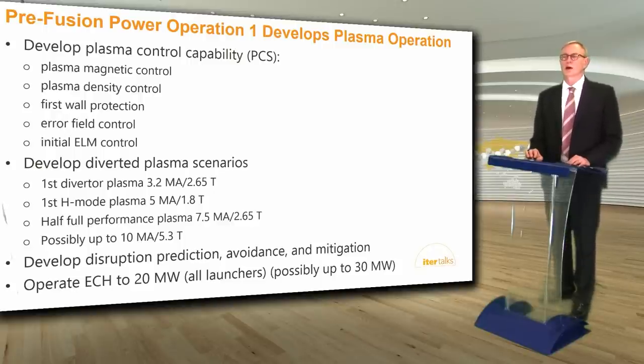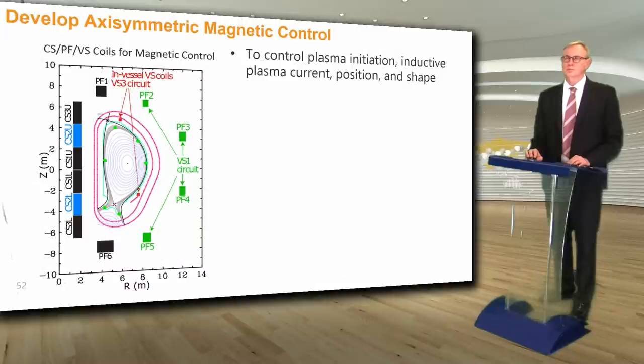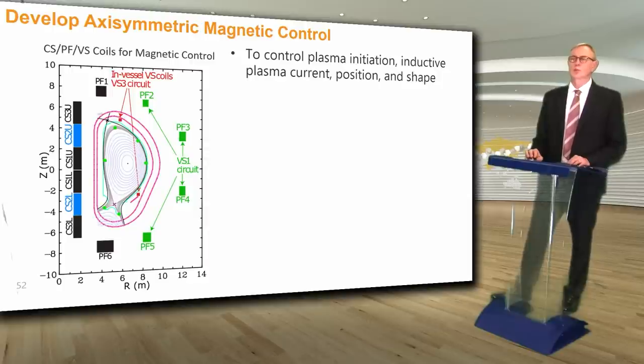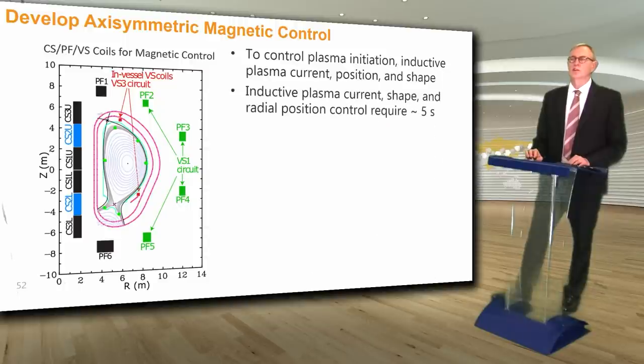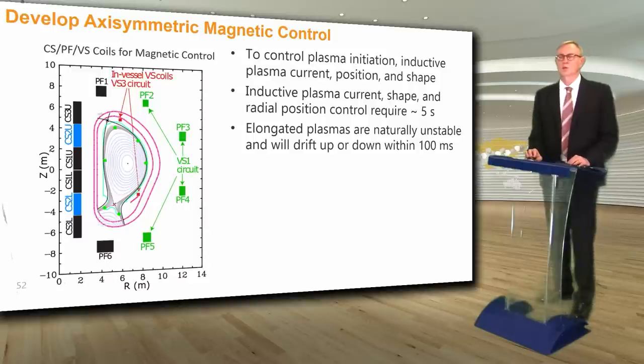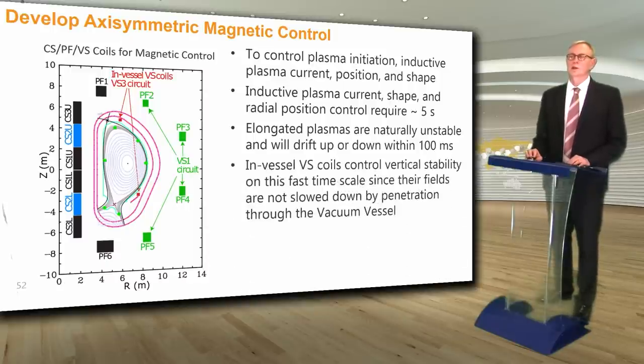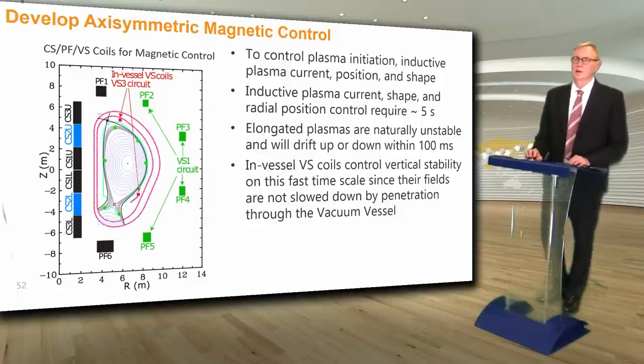The PCS will control the CS, PF, and in-vessel VS magnets to control plasma initiation, inductive plasma current, position, and shape. The inductive plasma current, shape, and radial position control need about 5 seconds of settling time. But elongated plasmas are naturally unstable and will drift up or down within about 100 milliseconds, so we need in-vessel VS coils to control the vertical stability on this fast timescale since their fields are not slowed down by penetration through the vacuum vessel. The vertical position is also controlled on a longer timescale with the slower ex-vessel VS1 system of PF coils.